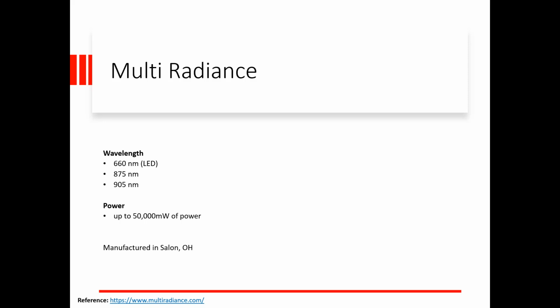But it is an FDA guideline and requirement that if you are using energy in the infrared spectrum, infrared meaning non-visible spectrum, it's obviously dangerous, and you guys saw the classifications. Now, this particular laser, they are a class 3 laser, but it is dangerous for them to use that device optically. So you have to have a guidance light. You have to have something that the physician can physically see so they know where they're pointing that device. In this case, they use a 660 nanometer LED, and they will claim the same effects as an Erchonia laser at 635 nanometers because they're both red.